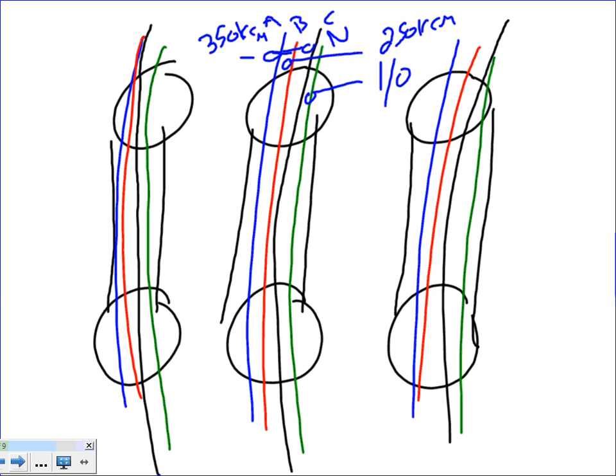Yeah, drums. And how many times did you guys wire a center tap delta? Never. Okay. Center tap delta, guys, is used mostly where 90% of your load is 3 phase and only 10% is single phase. A good example would be lift stations where you have multiple pump well houses, multiple pumps, all of them 3 phase, and you need just a couple of lights and receptacles. So take this one as a mental exercise and use it if needed.